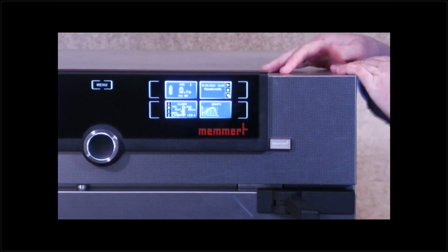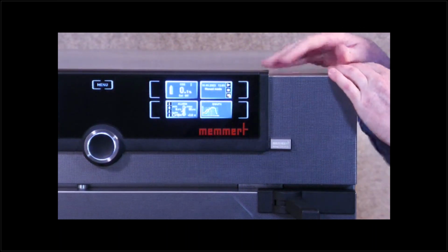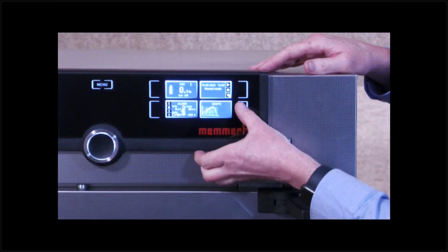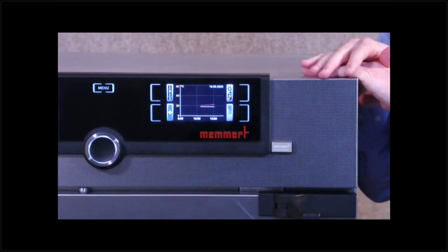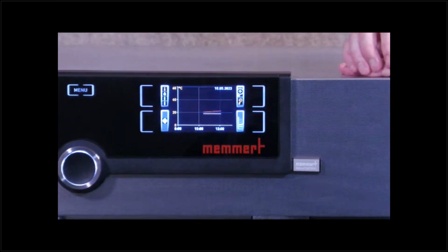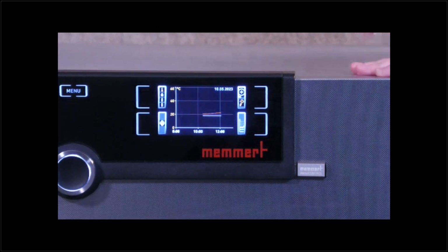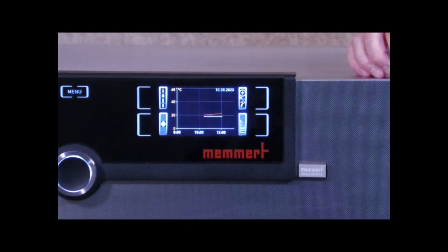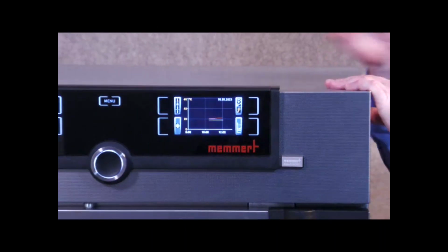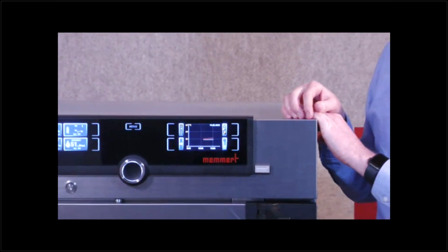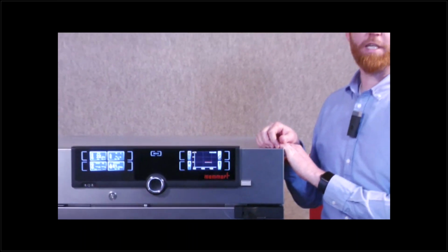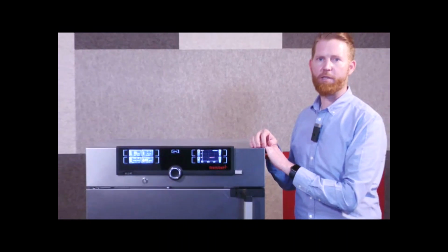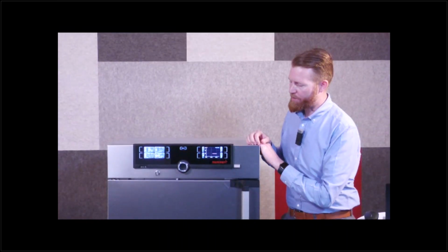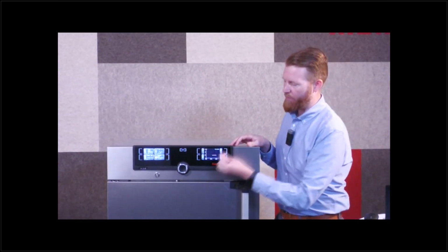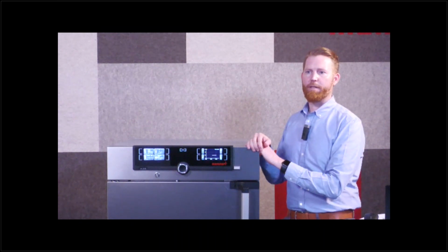In some units, there is also a possibility to check the graph of temperature or humidity or CO2. When you're arriving back in the laboratory after the weekend, you would like to know what happened during the weekend with the machine without reading out the complete internal data logging system. Then you can just have a look here at the graph directly.